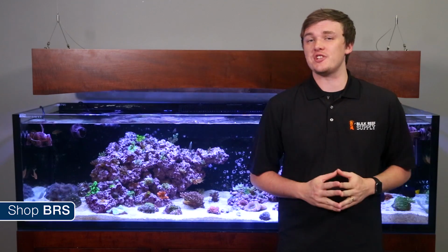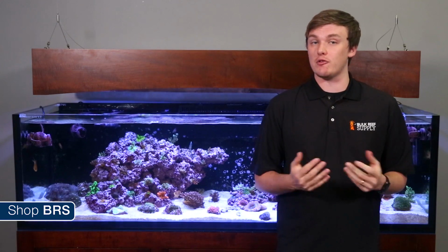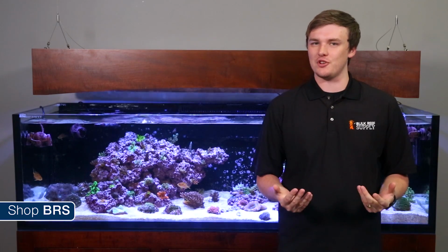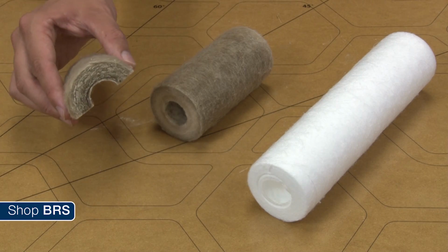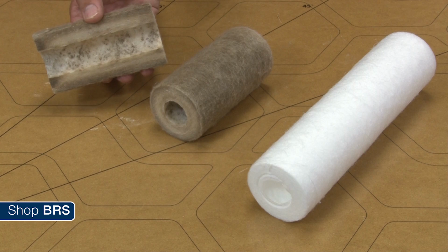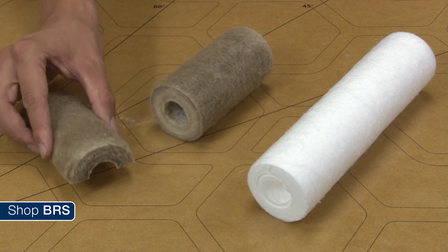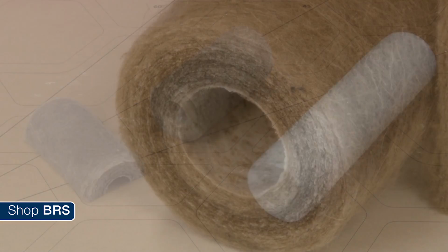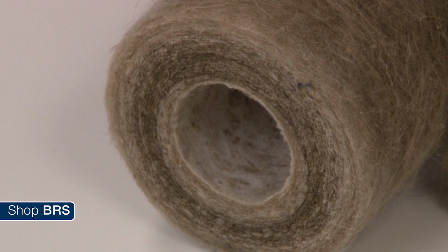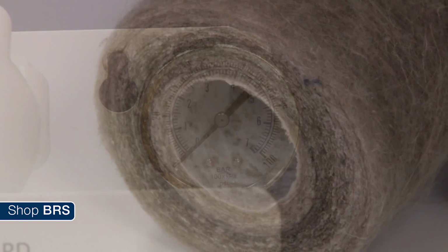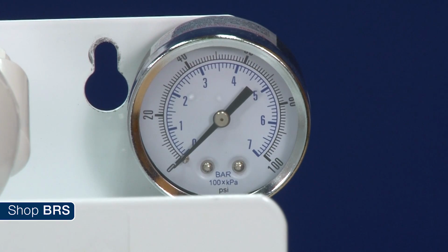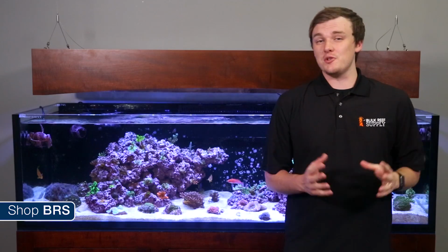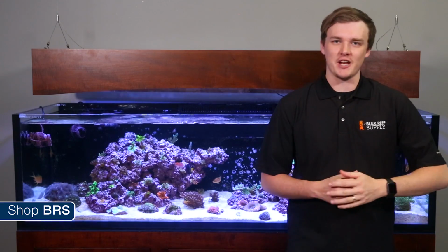So if you can't use TDS to determine when a filter needs to be replaced, how do you make that determination? Well, it's actually pretty simple. Sediment filters are designed to pull particulate matter out of the water, saving your more expensive filters like your carbon blocks and membrane from getting prematurely clogged. When this filter starts to go bad, it clogs, reducing the input pressure to your membrane. This can be monitored with a pressure gauge like those found in our upgrade kits and a good portion of our RO systems. Once you begin to notice a drop, it's time for new sediment filters.